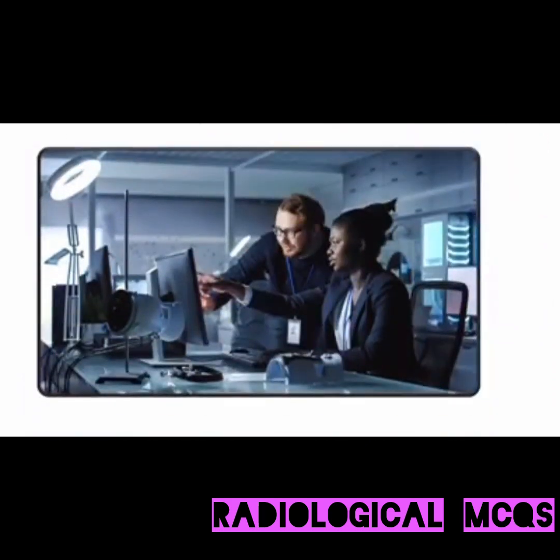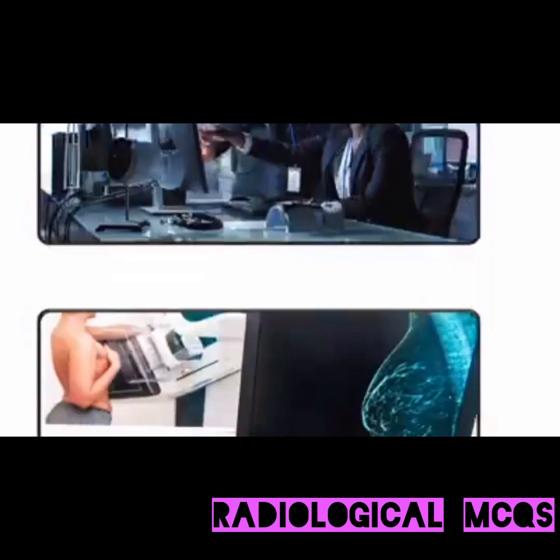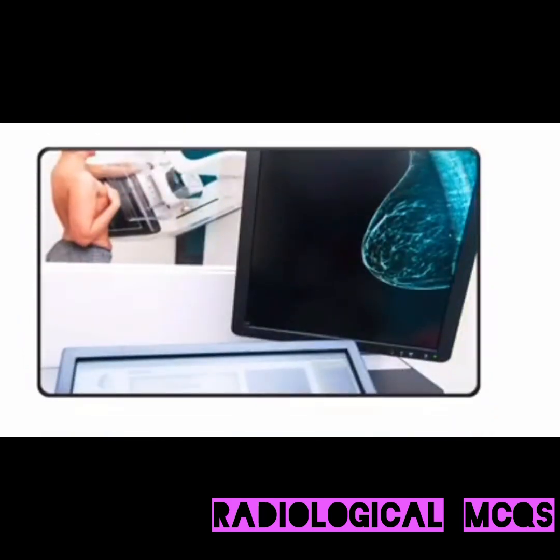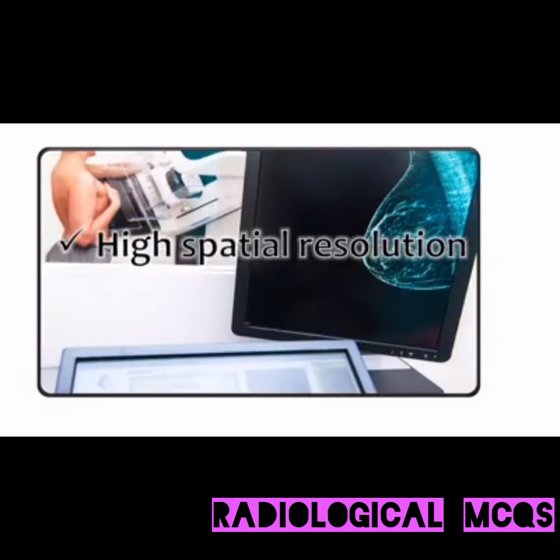The line focus principle is especially useful when producing diagnostic X-ray equipment. For example, an X-ray tube used for mammography needs a small anode angle since mammograms must have a high degree of spatial resolution.